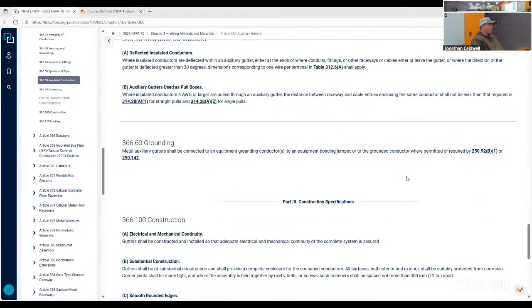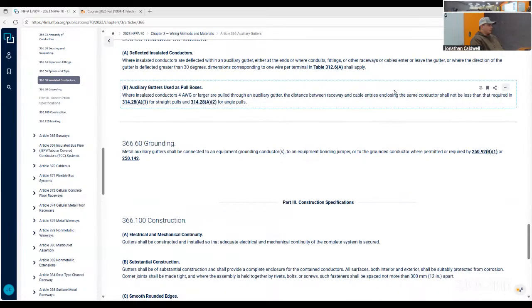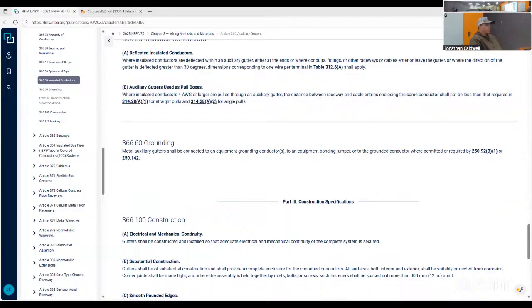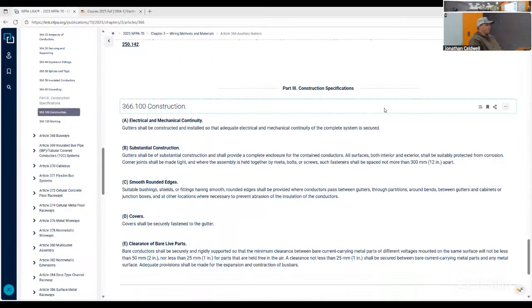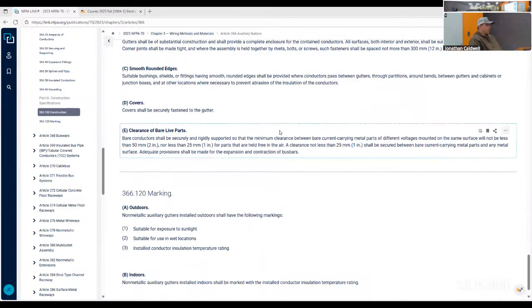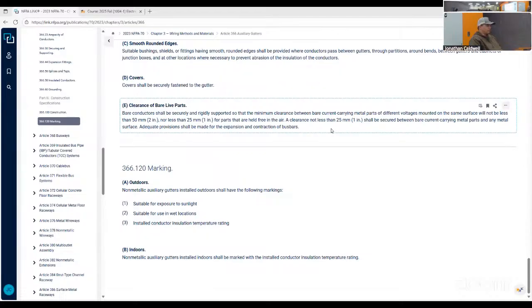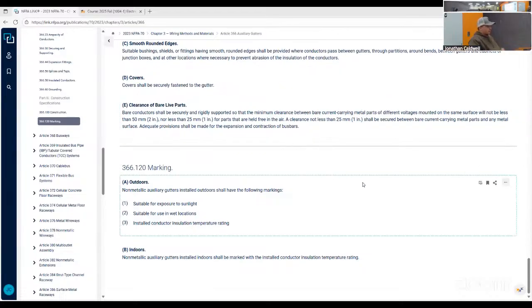So, grounding. Metal auxiliary gutters shall be connected to an equipment grounding conductor, to an equipment bonding jumper, or to the grounded conductor where permitted. And then construction: continuity, no rough edges, substantial construction, and clearance of live parts. And then it has to be marked for its use from the factory. Those markings are usually right in the center on the inside. That goes for most J boxes or any kind of metal box that you use, except for a four-square. Four-squares can be weird.